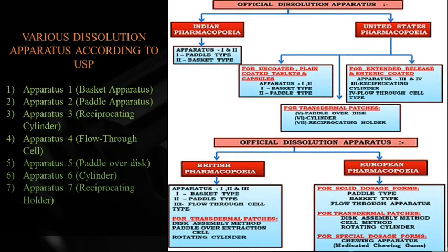Various dissolution apparatus according to USP: Apparatus 1 is basket, Apparatus 2 is paddle, Apparatus 3 is reciprocating cylinder, Apparatus 4 is flow-through cell, Apparatus 5 is paddle over disc, Apparatus 6 is cylinder, Apparatus 7 is reciprocating holder. According to Indian Pharmacopoeia, Apparatus 1 is paddle type and Apparatus 2 is basket type — opposite to USP. USP Apparatus 1 and 2 are used for uncoated, plain coated tablets and capsules.